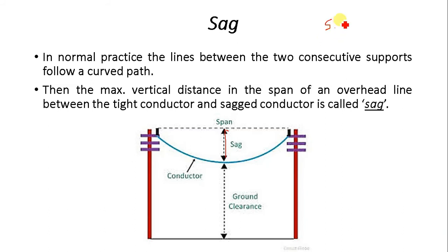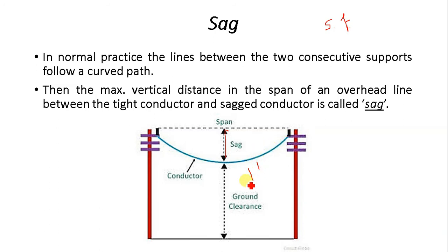The tension in the conductor is always limited by its ultimate strength, and that is why we consider a term called safety factor (SF). The tension in the conductor depends upon the diameter of the conductor, the material of the conductor, the sag, the wind pressure, and also the temperature. All these things must be considered while defining the ultimate strength of the conductor.